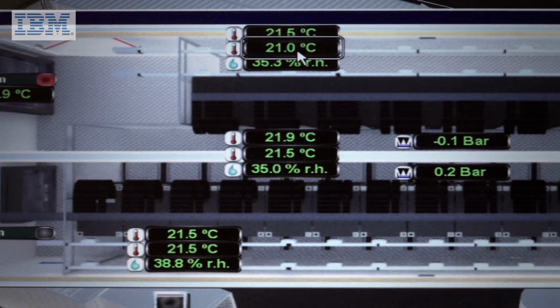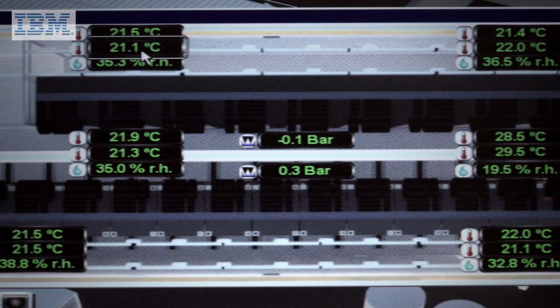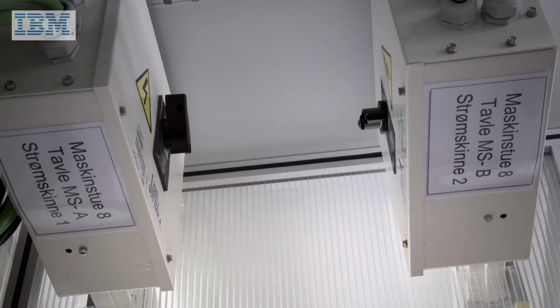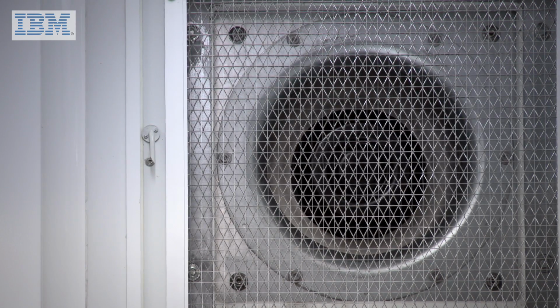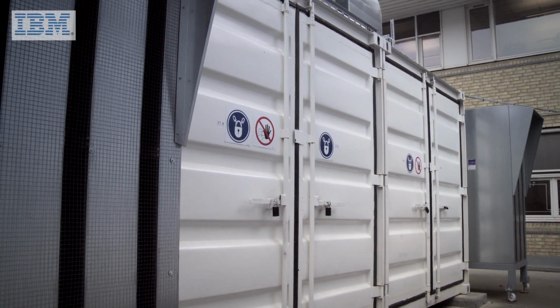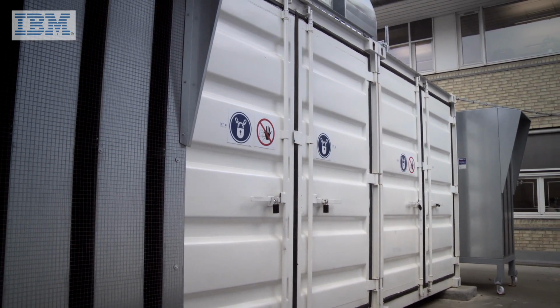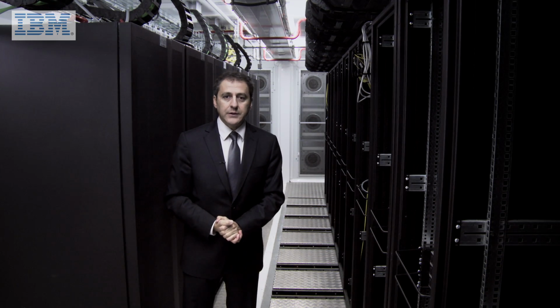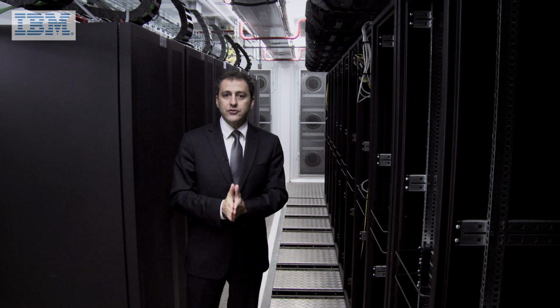The cold corridor, where all the racks are placed, is fed by dual power busbars with an A and B power supply independently, in a total tier 3 configuration. And all the racks are cooled by the natural free cooling system at the end, which is an attached module to this IT container module. This is the hot corridor area. This is the area where the two IT containers join.